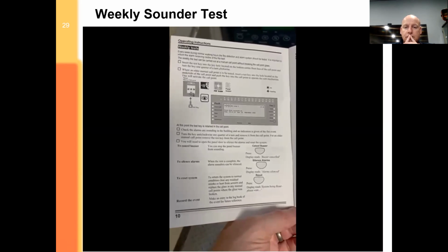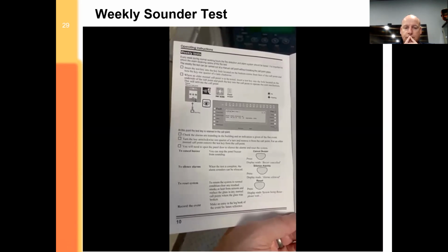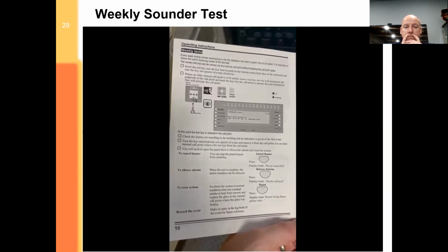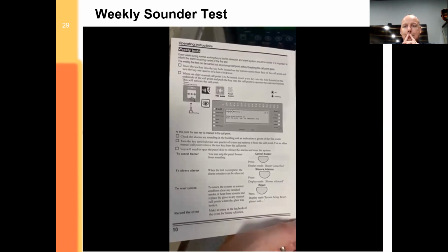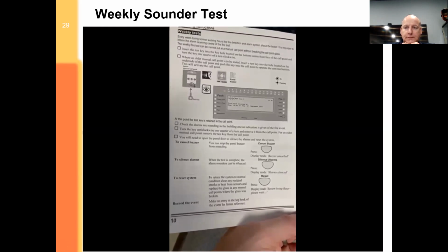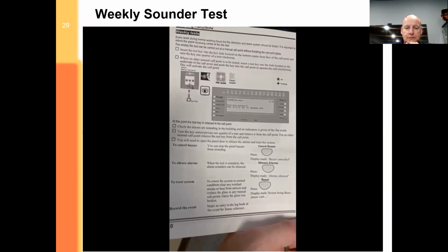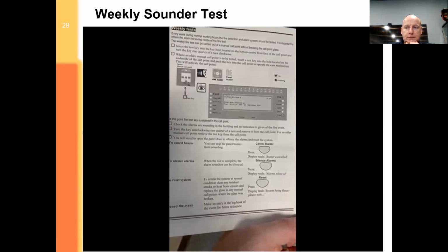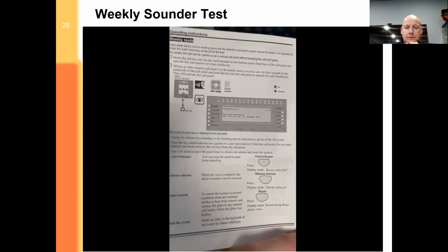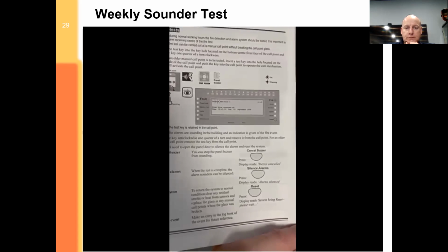On page 10 of the instruction manual, it discusses how to do the weekly test. The purpose of the weekly test is to make sure that all the alarm sounders can be heard, and at the same time to check the manual call points work effectively, so that if they are ever used, you know that one, the manual call point will do its job and set the alarm off, and then two, when the alarm has gone off, that people can hear it and take the appropriate action.